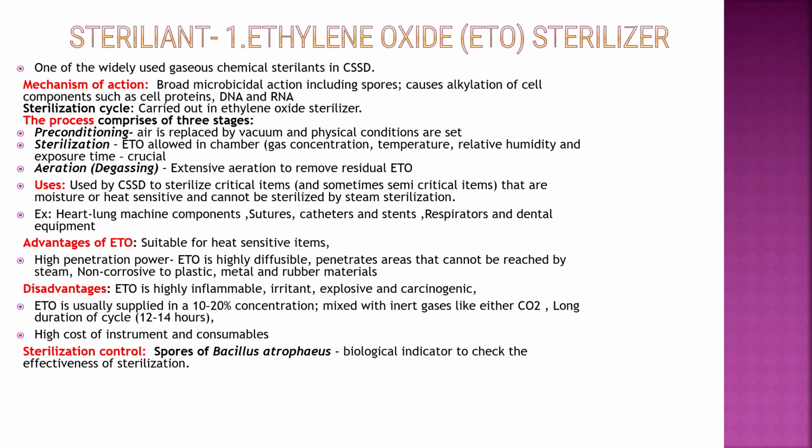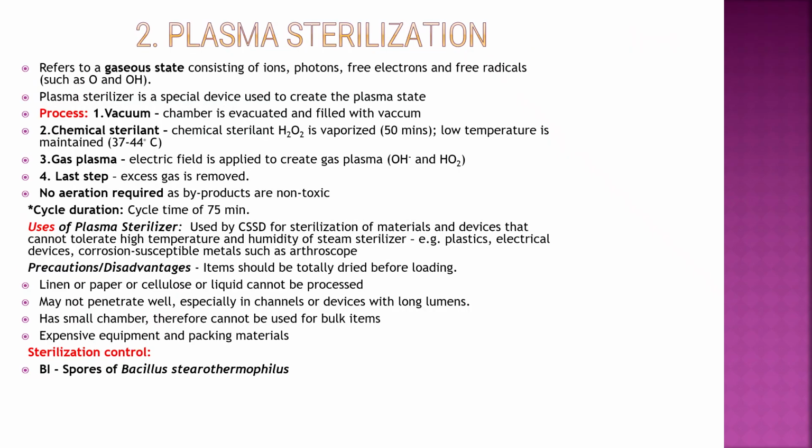ETO is usually supplied in 10 to 20% concentration mixed with inert gases like CO2. The cycle duration is long, 12 to 14 hours. High cost of instrument and consumables. Sterilization control: spores of Bacillus atrophaeus are the biological indicator.